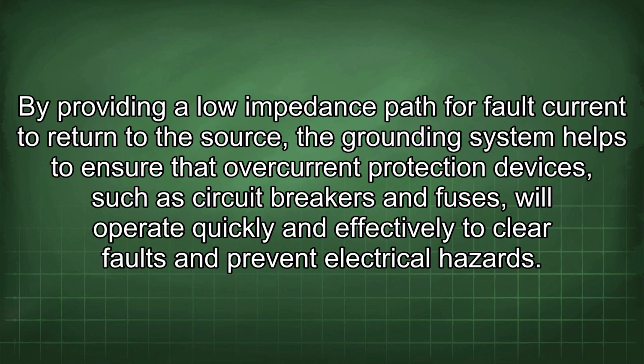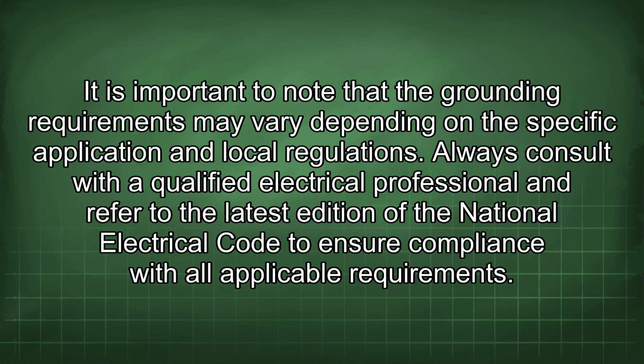By providing a low impedance path for fault current to return to the source, the grounding system helps to ensure that overcurrent protection devices, such as circuit breakers and fuses, will operate quickly and effectively to clear faults and prevent electrical hazards. It is important to know that the grounding requirements may vary depending on the specific application and local regulations. Always consult with a qualified electrical professional and refer to the latest edition of the National Electrical Code to ensure compliance with all applicable requirements.